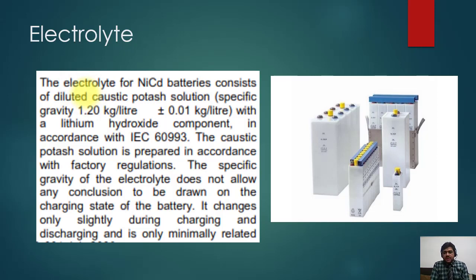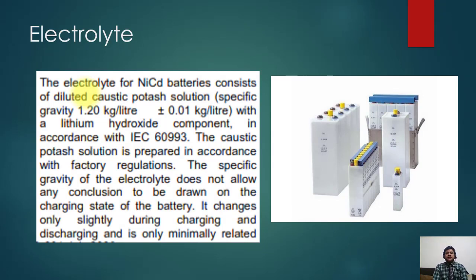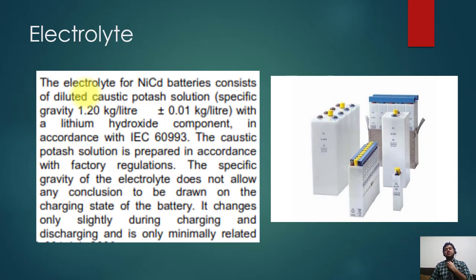Now for nickel-cadmium batteries: the electrolyte consists of a dilute caustic potash solution with a specific gravity of 1.2 kg per liter plus or minus, with a lithium hydroxide component in accordance with IEC 60993. The caustic potash solution is prepared according to factory regulations. Importantly, the specific gravity of the electrolyte does not allow any conclusion about the charging state of the battery — it changes only slightly during charging and discharging. This is different from lead-acid batteries, where specific gravity increases with charge.